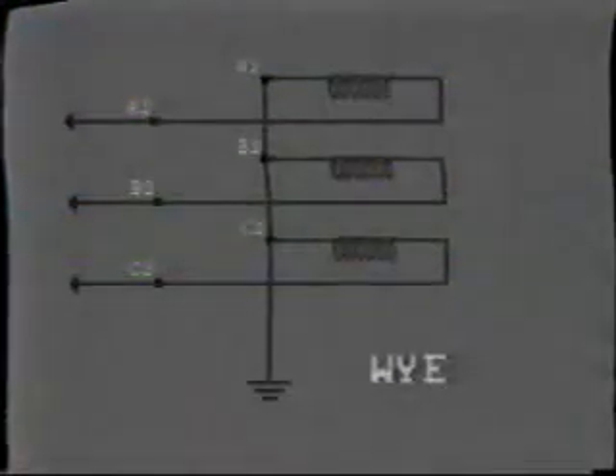The most common connection, Y, would look like this. The beginning of each winding, A1, B1, and C1, are all solidly connected together, and this neutral point may then be connected to ground, usually through an impedance. The other end of each winding, A2, B2, and C2, provides the three-phase output from the generator.